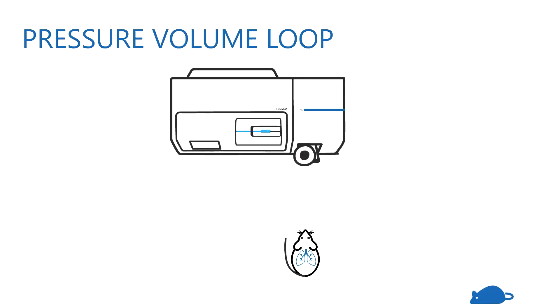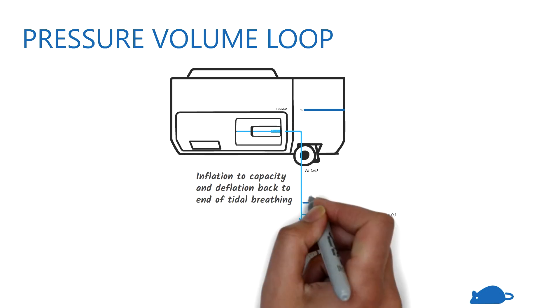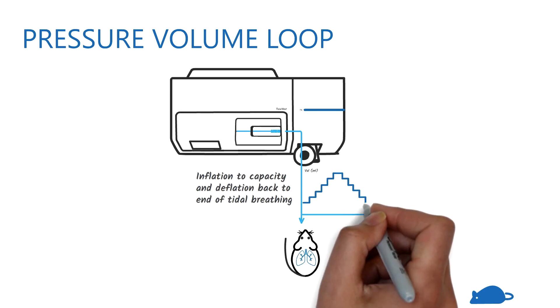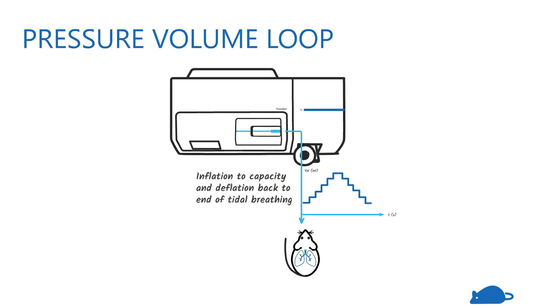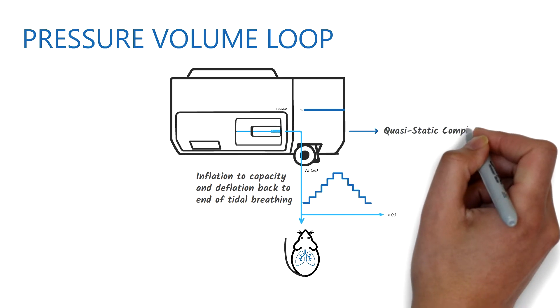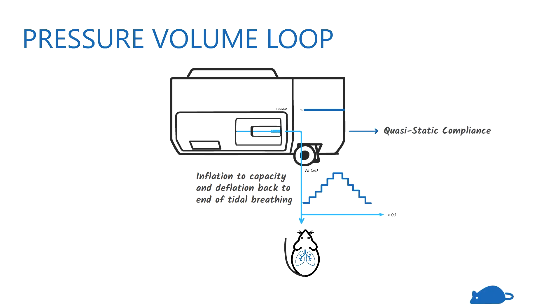In the pressure-volume measurement, the lungs are inflated to total lung capacity and then deflated in a stepwise manner. The flexiVent measures the quasi-static compliance of the lung across the entire inspiratory capacity.